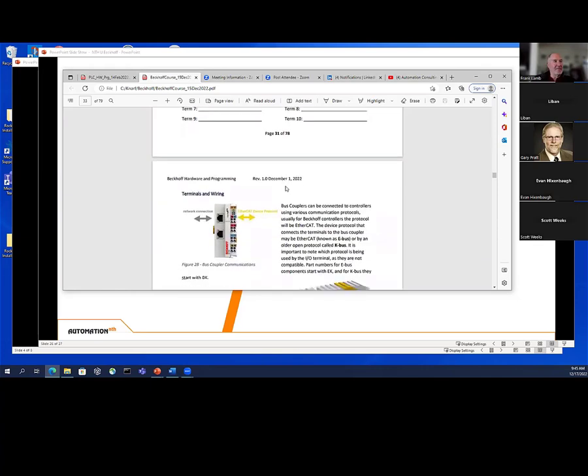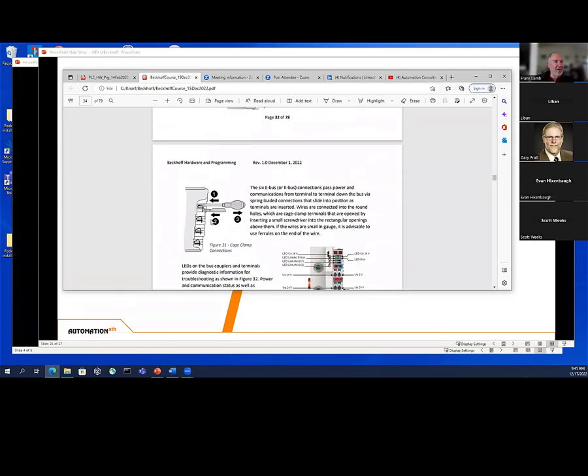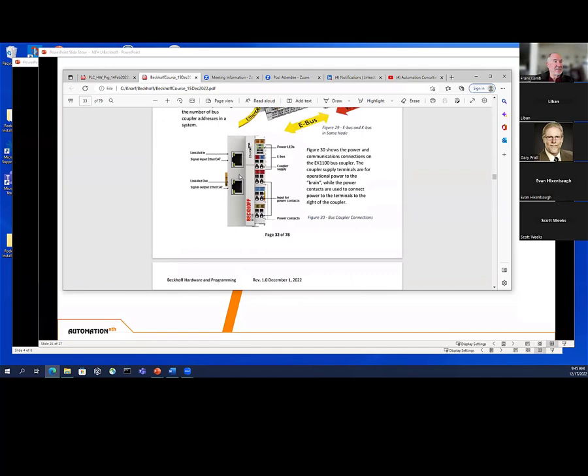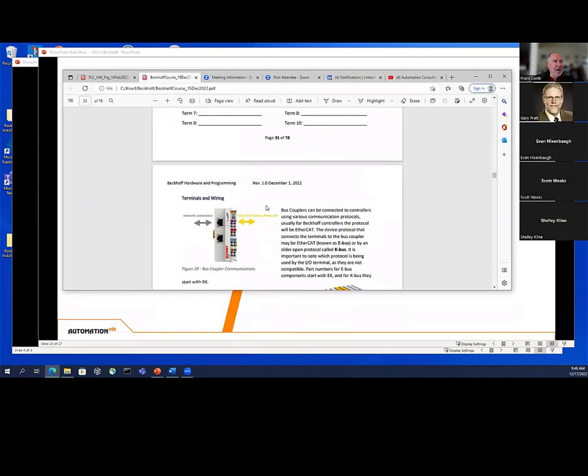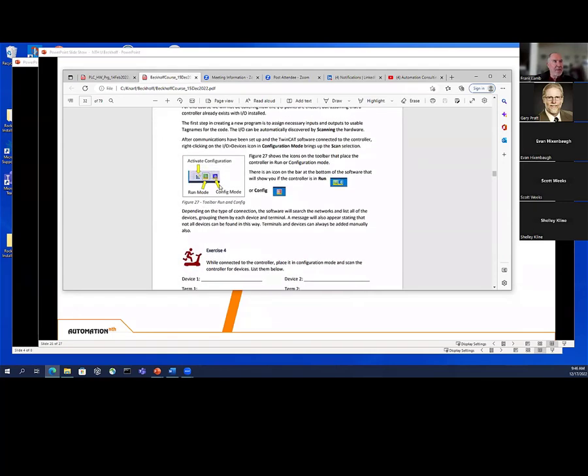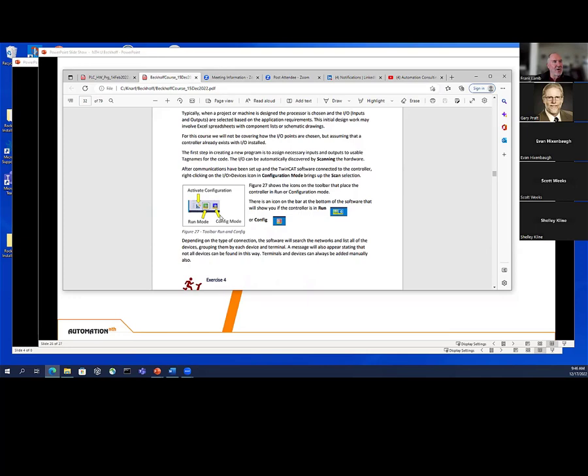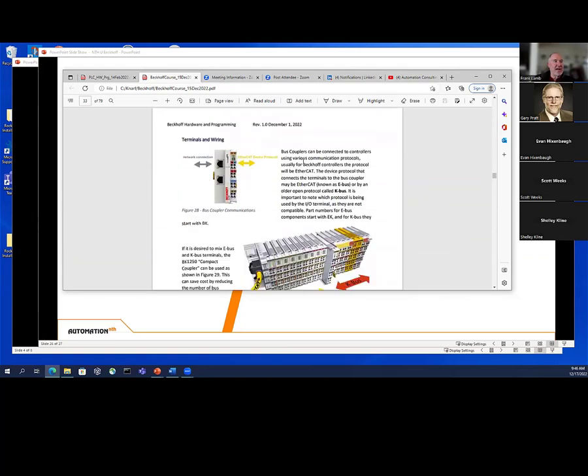I put a little diagram in for that. Cage clamps — it's actually pretty easy to wire with these. I used to not like them because depending on the gauge of wire, I didn't use a lot of ferrules in the nineties, and when cage clamps first came out they'd break wires. But now I use ferrules on pretty much everything, so they work really well with these Beckhoff modules. Then scanning IO — this is really important. This is connecting up to the controller and pulling all the terminals in automatically. That diagram I showed you before is actually one I created in PowerPoint — I blew it up big, copied it, and shrunk it down in the document.